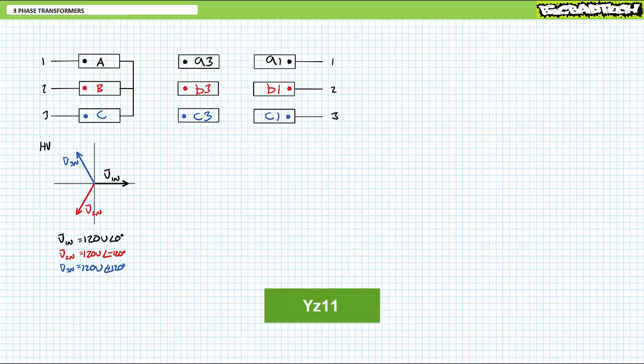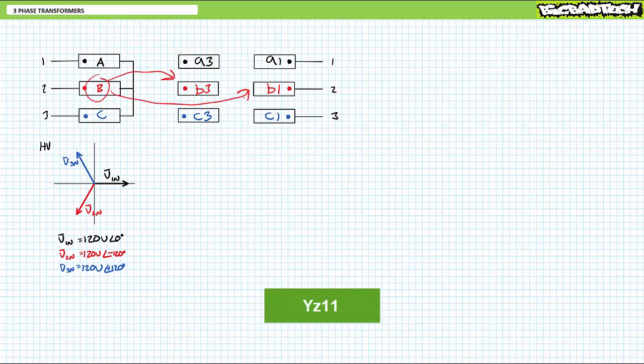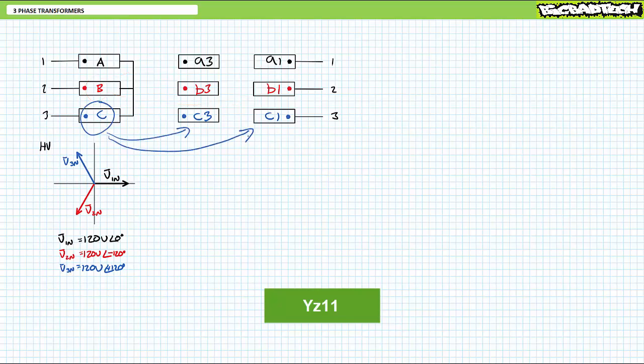The low voltage side using a zigzag connection has two windings per phase for a total of six. High voltage winding capital A maps to both low voltage windings, lowercase a1 and a3. Similarly, high voltage winding capital B maps to both low voltage windings, lowercase b1 and b3. And finally, high voltage winding capital C maps to both low voltage windings, lowercase c1 and c3.